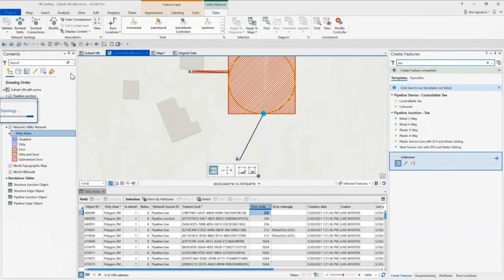So now I'm going to switch to 1Integrate. 1Integrate is 1Spatial's rules engine, which we use to automatically check the data and also fix it using no-code rules. We're running a series of rules checking the data against the utility network rules. In this case, we're first checking for missing T's across the entire 150,000 feature data set. The first percentage we have is 41% correct. Then, after applying a rule to automatically fix those T's and create them where missing, we get a 96% correct score.